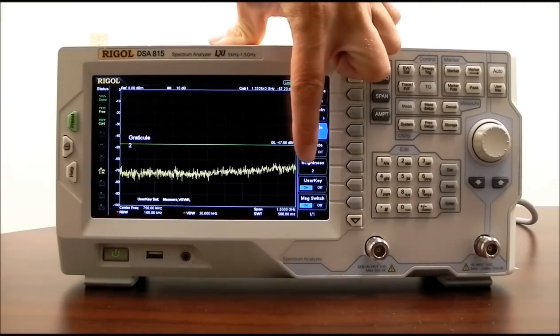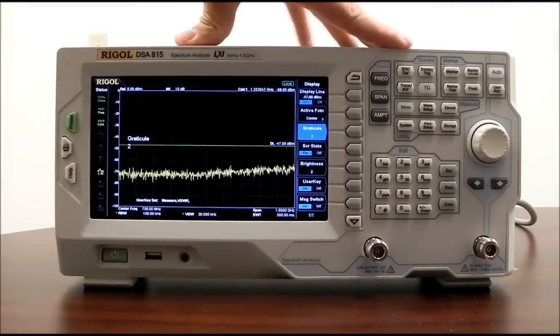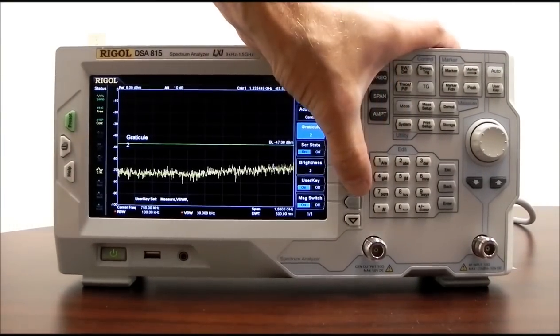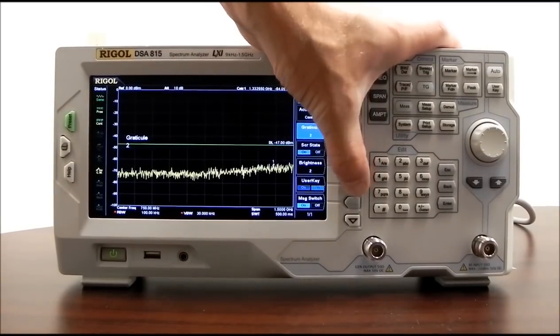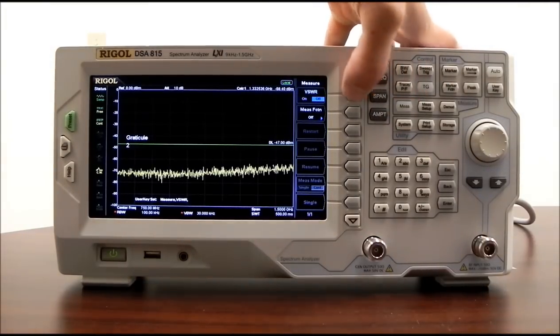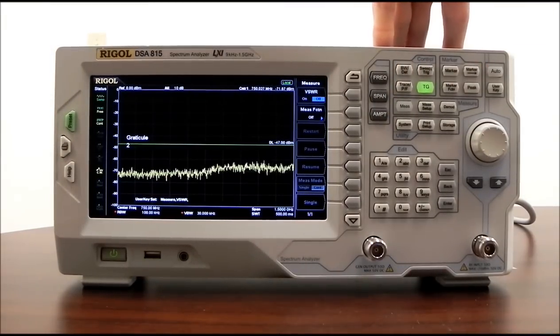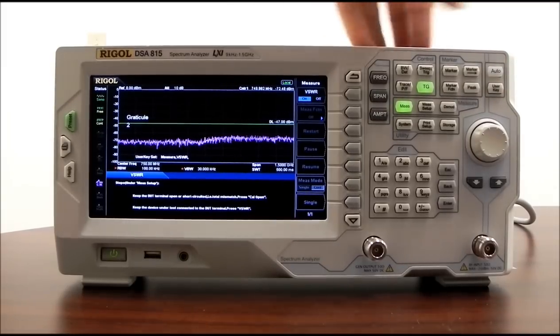We can enable the user key. User key is over on the right-hand side. Basically, when you enable the user key, you can set it to go into an area as a quick jump to that menu. So if we disable the user key, now let's enable the user key, and let's go to measure, and we'll enable VSWR, and we'll press the user key on. And so now you'll see that if we press the user key, we'll go back to the VSWR.